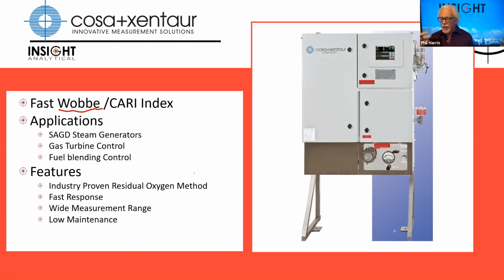Typical applications we see for this technology are things like in Alberta, certainly at SAGD on steam generators. We want to get that air to fuel ratio right, especially if we're getting fuel that can sometimes come in fairly rich and hot. Similarly for gas turbines, which don't like to see drops of liquids come in with them or really rich fuels all of a sudden - if they do, they can get too hot and damage the turbine blades. So typical application is burner control, where we're either doing fuel blending or trying to control large burners like turbines and SAGD steam generators, to get the best efficiency possible.